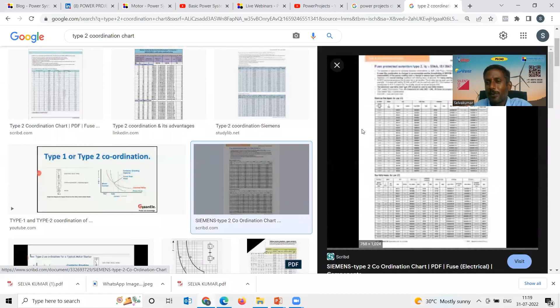When you have type 2 coordination, you are protecting the protective equipment as well as protecting the equipment which is to be protected. Let me repeat: in type 2 coordination, you are protecting the equipment which is to be protected, which is the motor, and you are protecting the equipment which is protecting, which is the circuit breaker or whatever it is. That's basically the purpose of type 2 coordination.